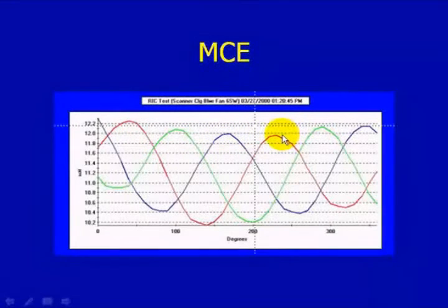Once we've found a correlation between the MCE and the Emax, and maybe vibration equipment, we can then secure this motor and perform a visual inspection. If we find that it's a soft foot issue, we should fix the soft foot issue and then restart the motor and do our tests again with the Emax and with the MCE and verify that that condition has significantly decreased.